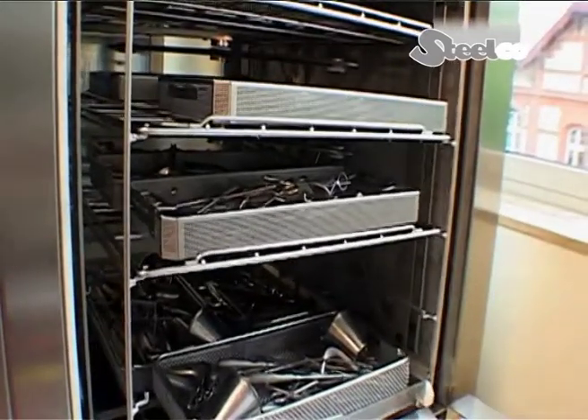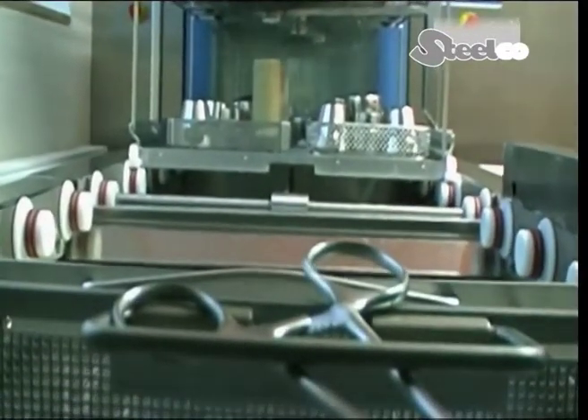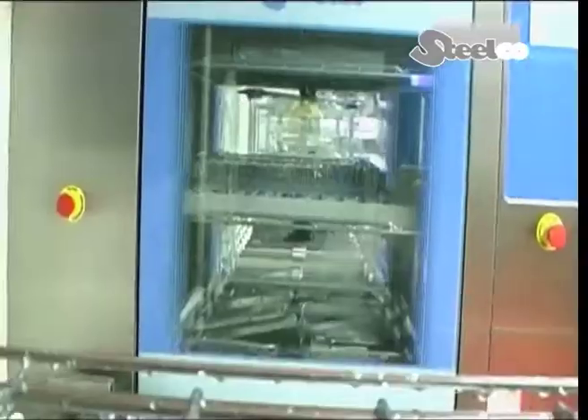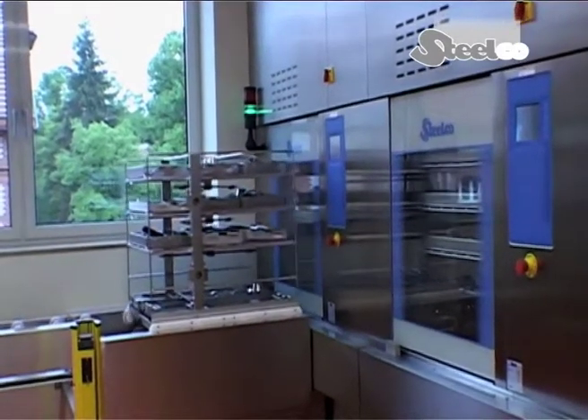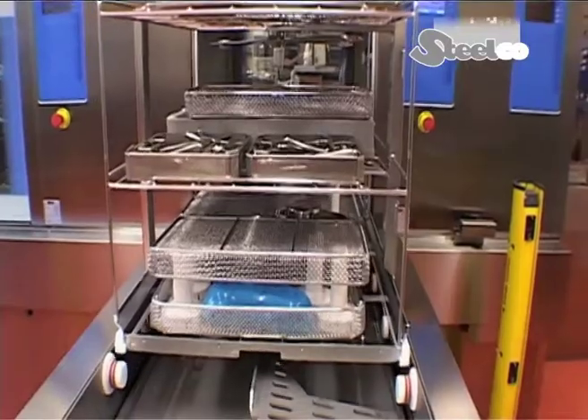After the instrument sets have gone through the DS-1000 pre-cleaning machine and through the US-1000 ultrasonic cleaning process, the automatic transfer system ATS leads the basket to one of the three free DS-1000 washer disinfectors. Sensors supervise the correct positioning of the basket. After the basket has been conveyed fully automatically into the cleaning and disinfection machine, the wash program planned for the specific load starts immediately.